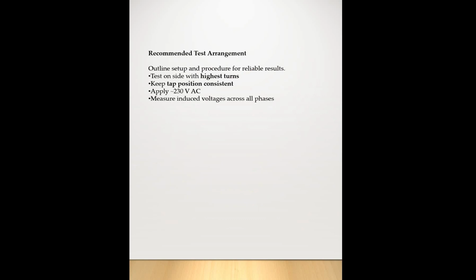core geometry. Okay, so the recommended test arrangement is to outline the setup and procedure for reliable results. Test on the side with the highest turns. Always perform the magnetic balance test on the highest winding turns, keep the tap position consistent, and apply 230 volt and measure the induced voltage across all phases.